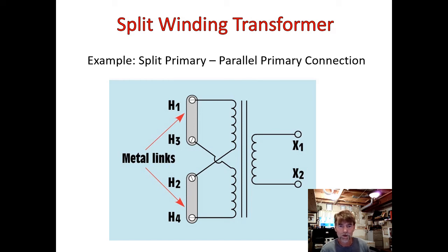So now you can see that by crossing those two center lines, we can comfortably recognize how these two coils get placed in parallel by jumpering 1 and 3 together to be one pole of, so if it's a DC circuit, that would be, say, the positive terminal, and then H2 and H4 connected to the negative terminal. Okay, of course, we're talking about transformers. Transformers don't work in DC. It has to be AC. Okay, but I'm trying to help you recognize, let me just draw this. If we were to complete the circuit out here to our, and I will show it as an AC power supply because it must be.